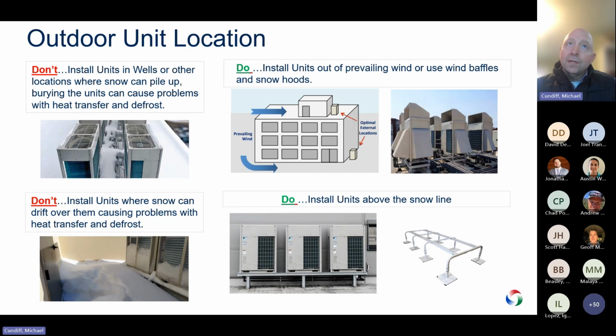So we have wind baffles that you can buy as an accessory, including the snow hoods up there. So those, Daikin provides those. There's other third-party manufacturers that provide them too. Really, the thing is to keep the wind off of the coils as much as possible. Bottom right, do install the units above the snow line. You can do field fabbed stands to get them up above the snow lines. There are other manufacturers like Bigfoot stands and things like that people use too, but just making sure that those things are not in a place where snow is going to drift up on them and cover them over time.